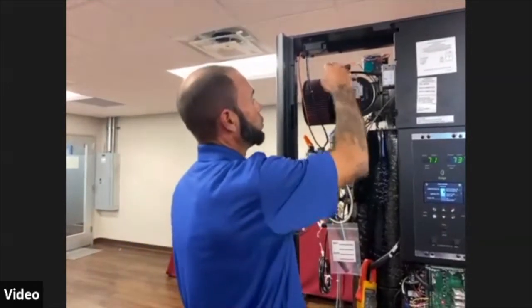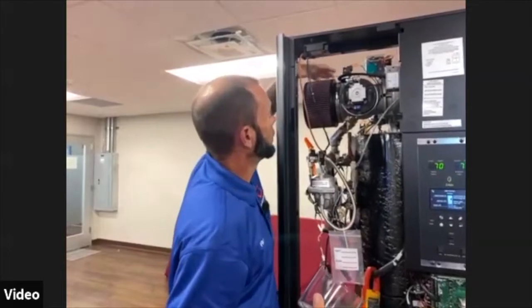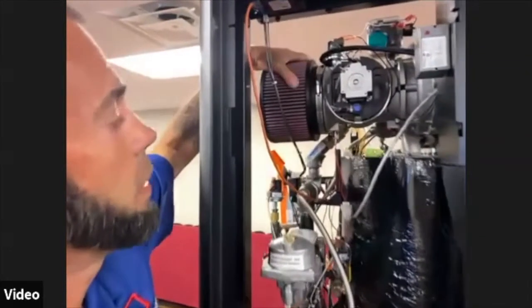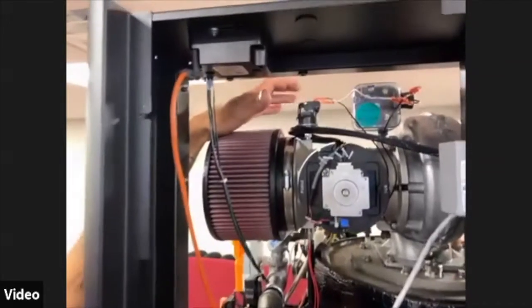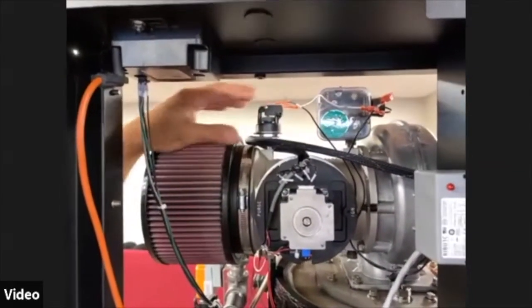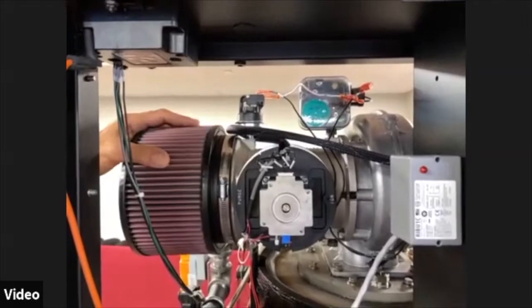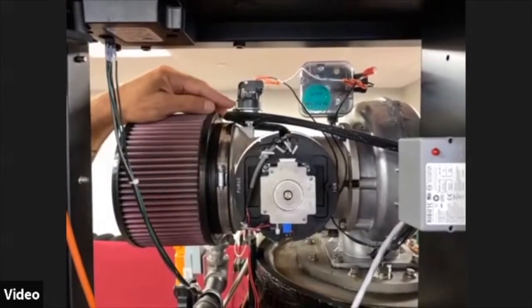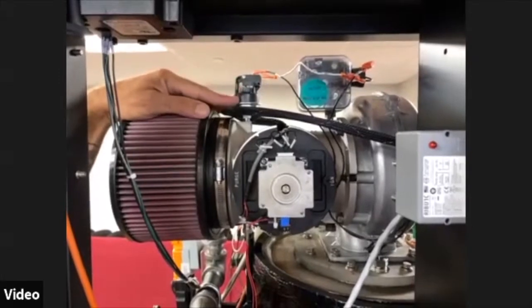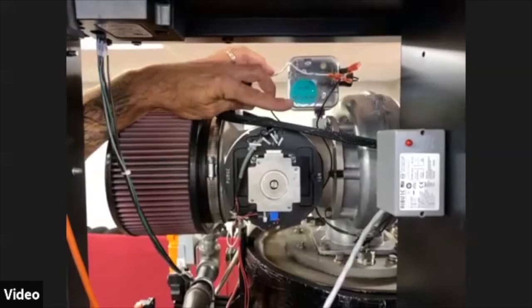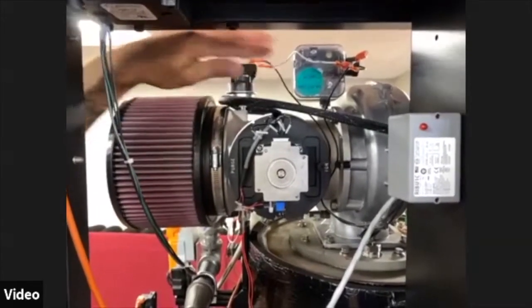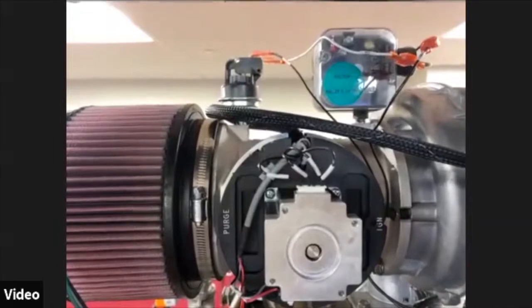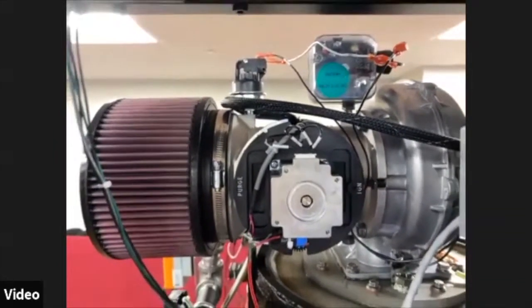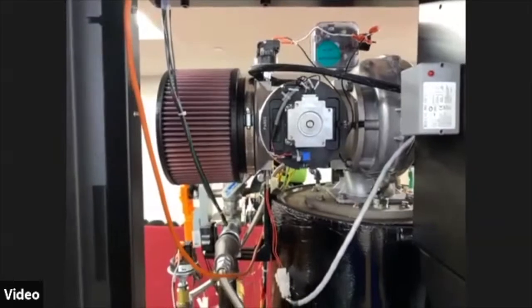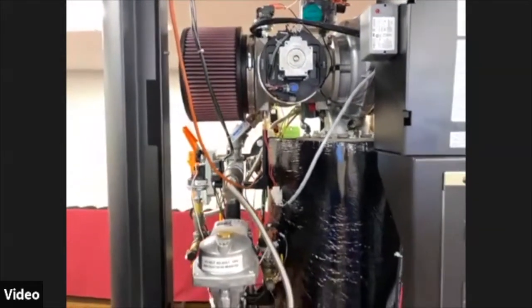Sitting on top of the air fuel valve would be our blocked air switch. So in the event that our filter was completely dirty and we weren't getting any air through here, this switch could potentially be open. If the switch is open, you'll get a blocked air fault and the boiler obviously will not run. 4.5 inches of water column is what the switch is set at. Air proving switch, our air proving switch is set at 0.16 inches of water column, very minimal. So again, if the blower doesn't run, the air proving switch doesn't prove, the boiler will never go into the rest of its sequence of operations.